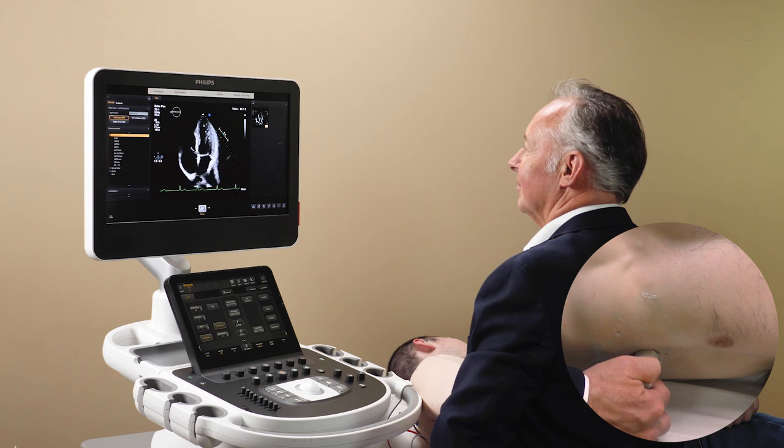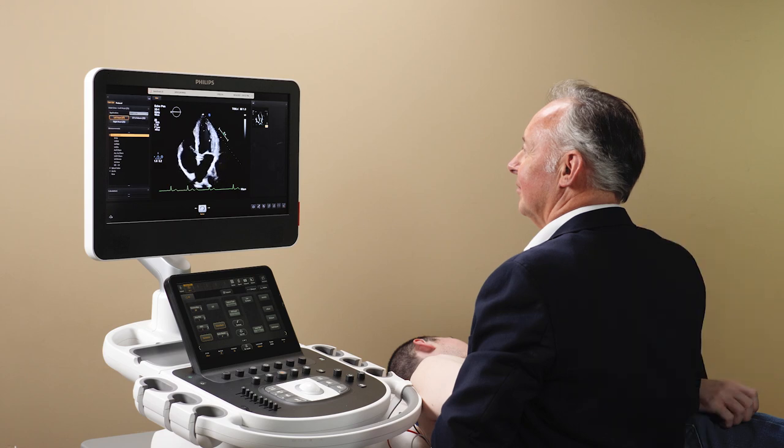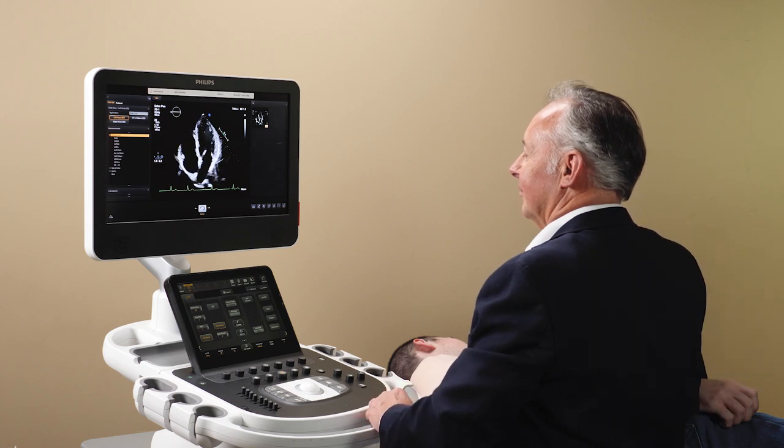Start from an apical 4 chamber view and rotate the probe slightly counter-clockwise until the base and the length of the left atrium is at its largest size. Press ACQUIRE.